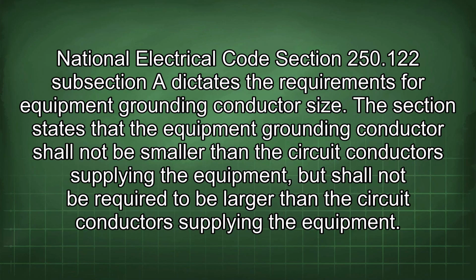National Electrical Code Section 250.122 subsection A dictates the requirements for equipment grounding conductor size. The section states that the equipment grounding conductor shall not be smaller than the circuit conductor supplying the equipment, but shall not be required to be larger than the circuit conductor supplying the equipment.